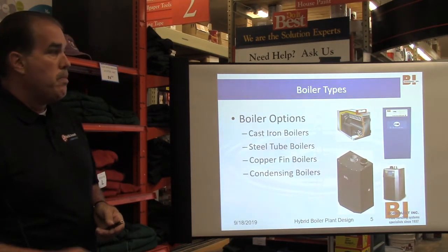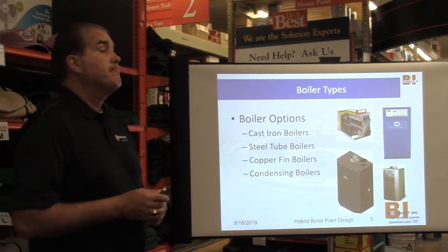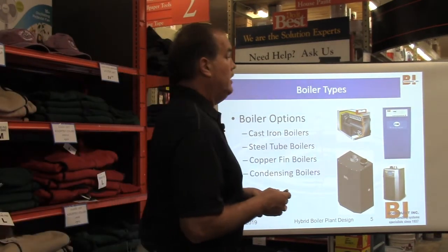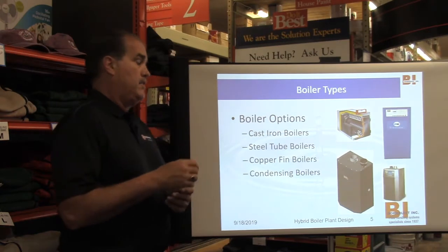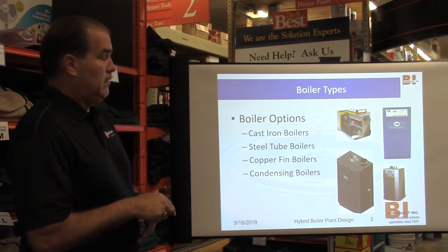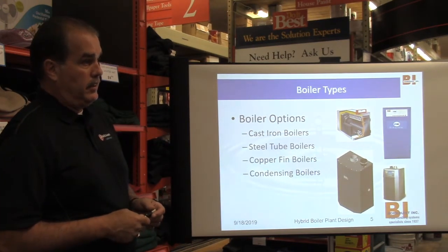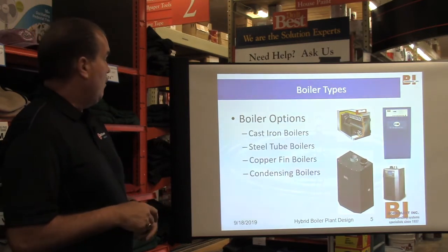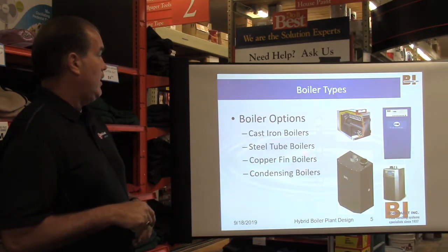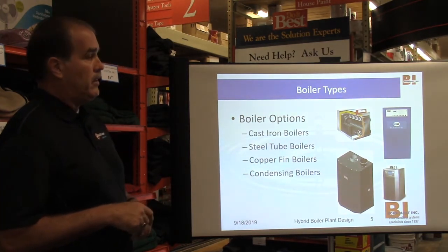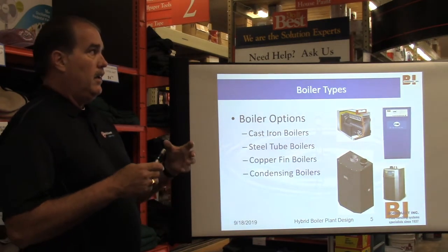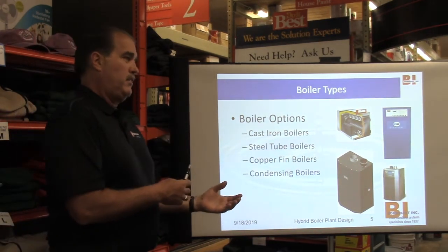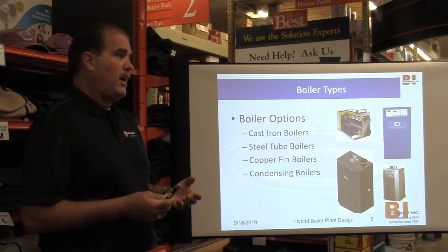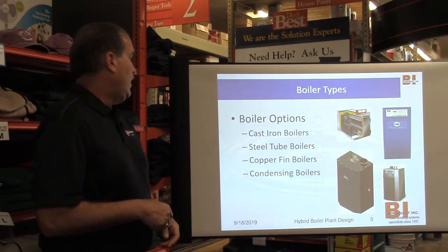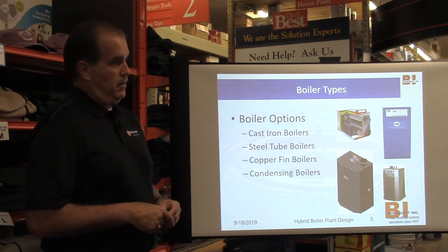Are these interchangeable? These boilers, can you change one out for the other? It depends on the application. A steam boiler, no. A steam boiler is a steam boiler. Water boilers, which is what we're talking about here. Now, a steel tube boiler can be a steam boiler. You don't see it so much on the residential side. It's more on the commercial side. A copper fin boiler will not be a steam boiler.